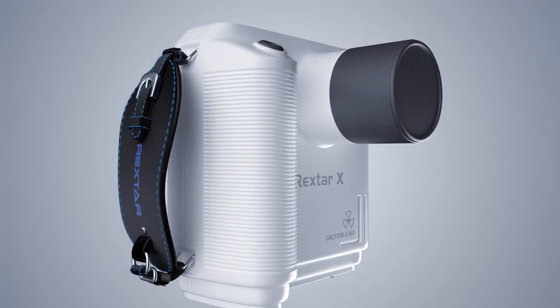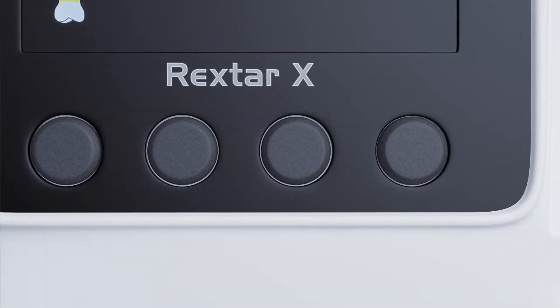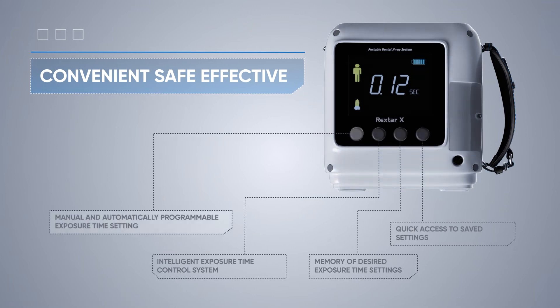Rextar X is easy to use. It has four buttons on the front of the panel under the LCD display. The modes of typical cases are set in these four positions. For each of them, you can manually set and save the desired exposure value.